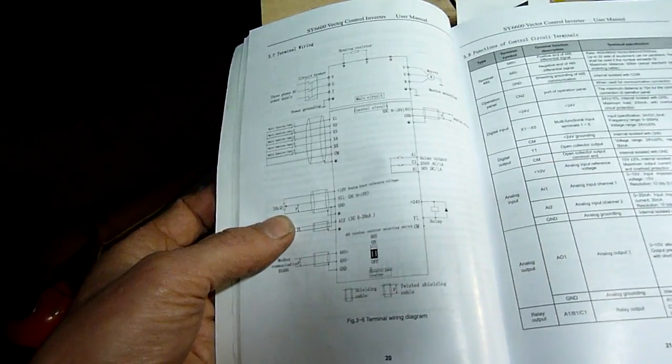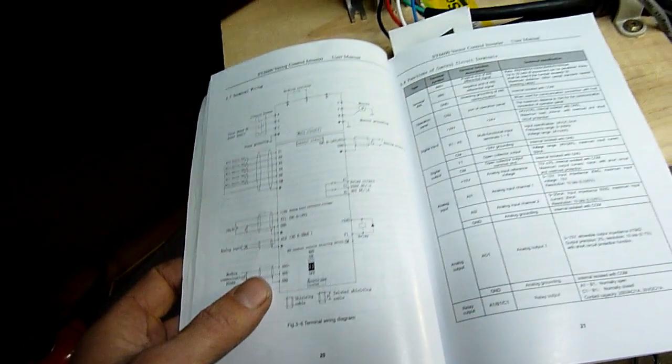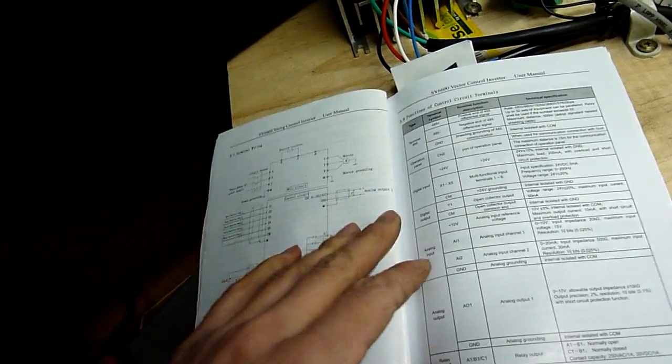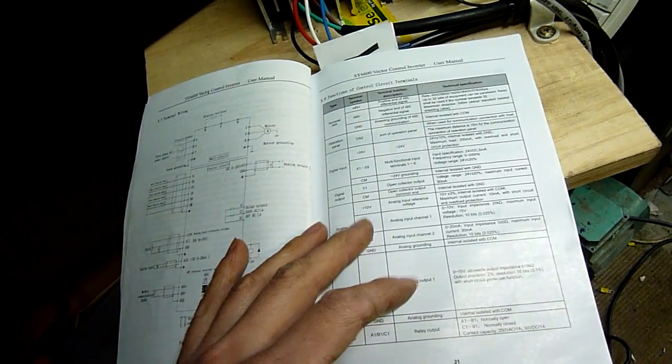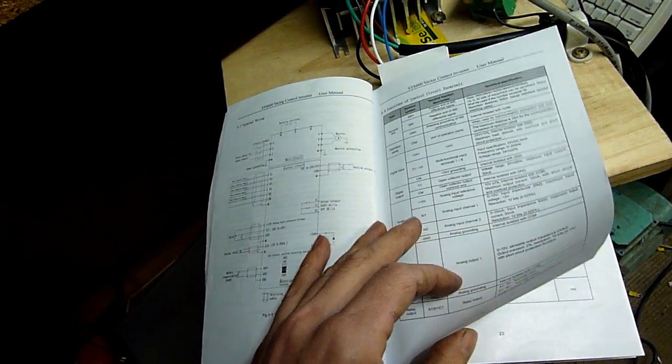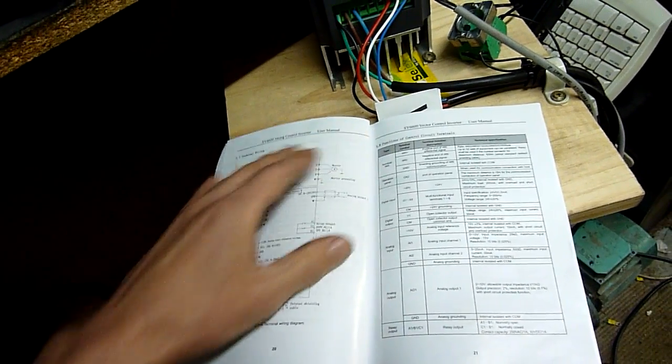Analog input again, that's external potentiometer, I don't need it in this case. I just keep it locked at 50 hertz with a one second ramp up. Motor just naturally coasts to a stop, no injection braking, nothing fancy. I'm not going to do anything stupid and really tax this drive, plus it's a tyre fitting machine. I don't want ridiculous amounts of start-up torque or anything, I actually want to start off a little bit gentle, and then ramp up.